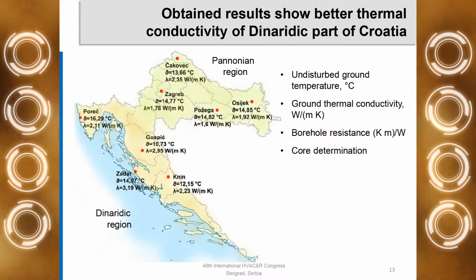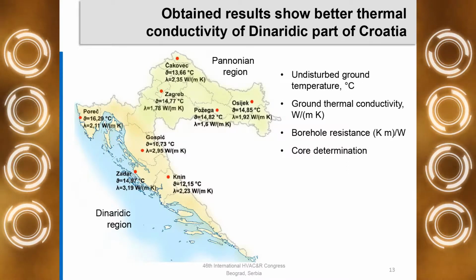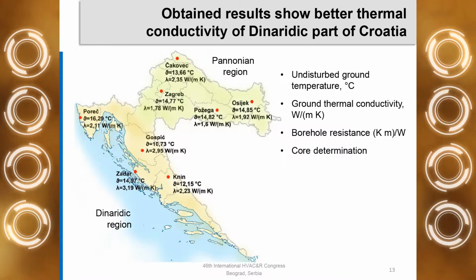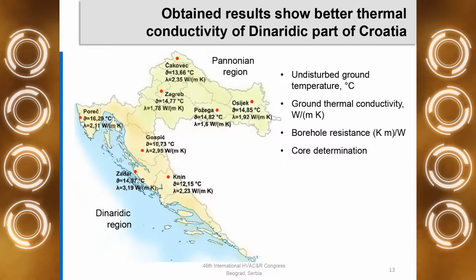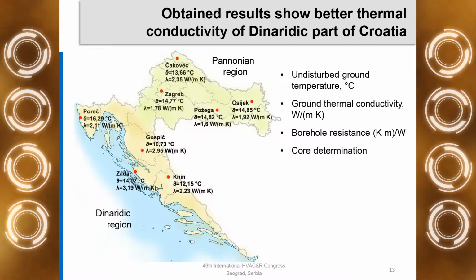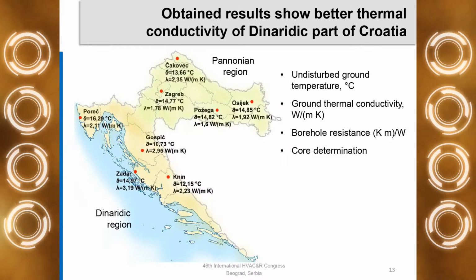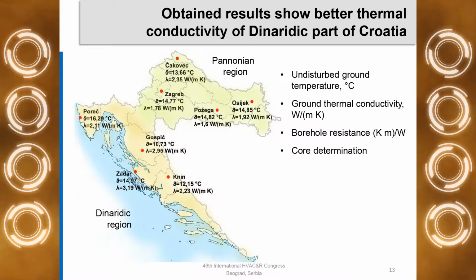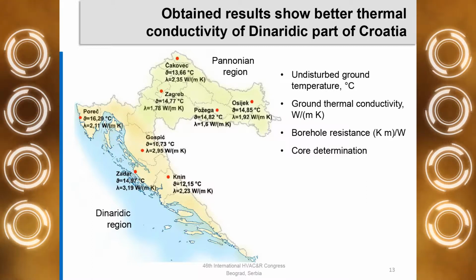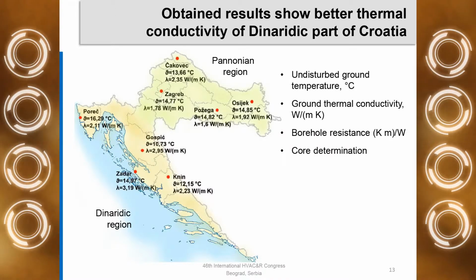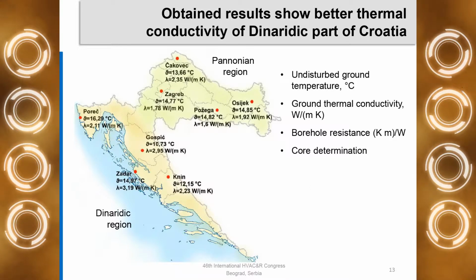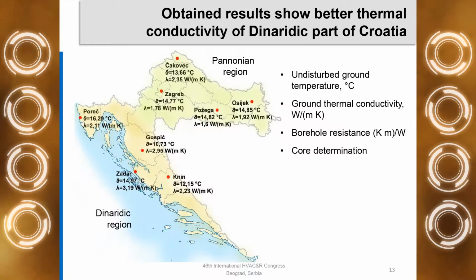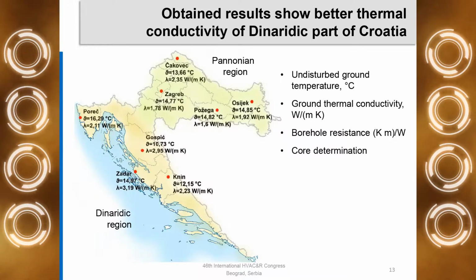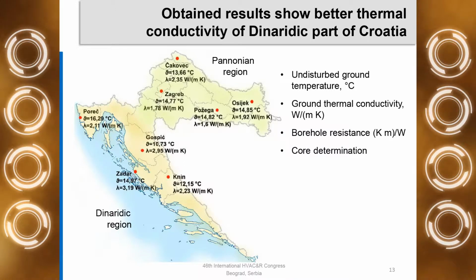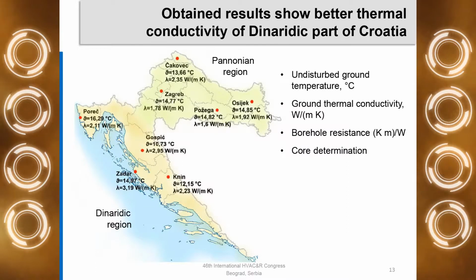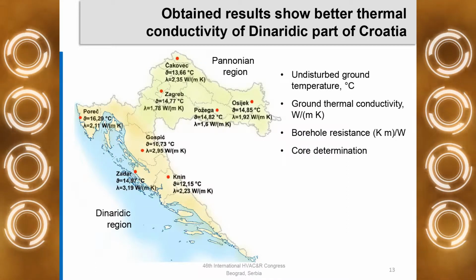If we observe all locations that were used during the project, we can clearly divide Croatia into 2 parts, one belonging to the already mentioned Pannonian region, and the other so-called Dinaridic region that is based on the Adriatic carbonate platform. By observing the values obtained, we can see that in the Dinaridic region, thermal conductivities of the underground are slightly higher than those found in the Pannonian region, and also the undisturbed ground temperature is highest in the localities located on the Croatian Adriatic, while in the Pannonian region, undisturbed ground temperature is basically constant around 15 degrees Celsius. This is an area that was represented by lower core samples that were mainly different kinds of rocks found on the locations.